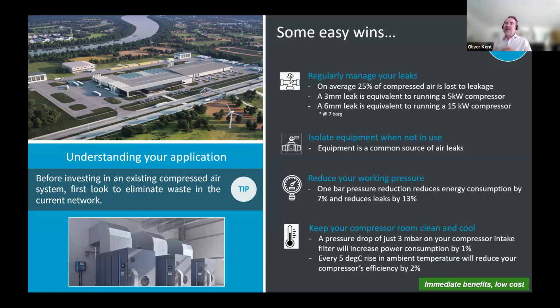But also, as a side effect, by reducing your working pressure, you reduce the amount of leakage as well. So by reducing your working pressure by 1 bar, you will reduce your direct energy consumption by 7%, but you will reduce your leakage by a further 13%.